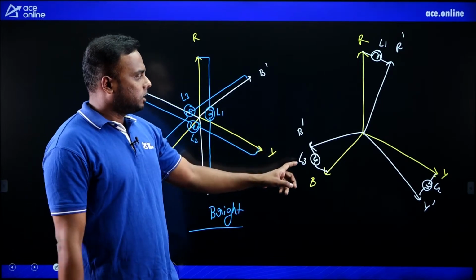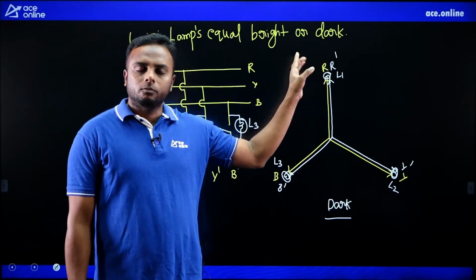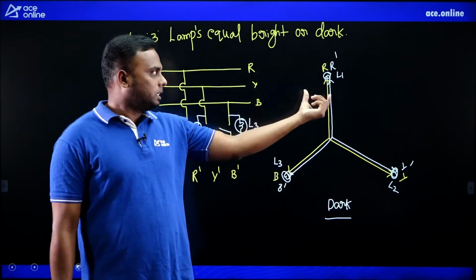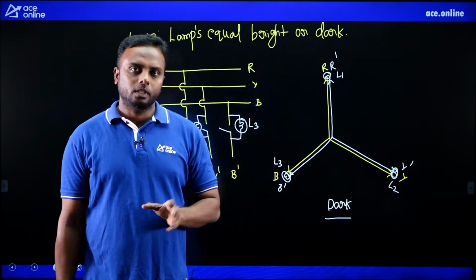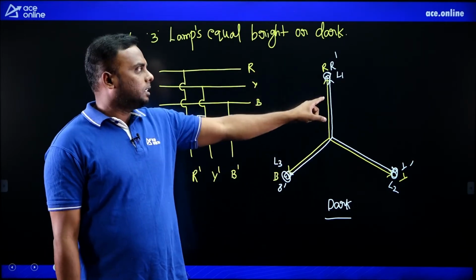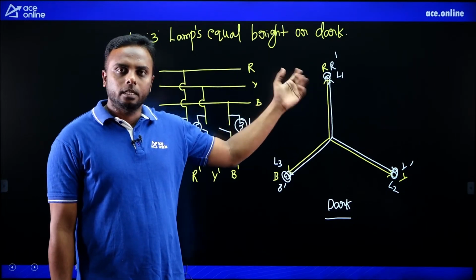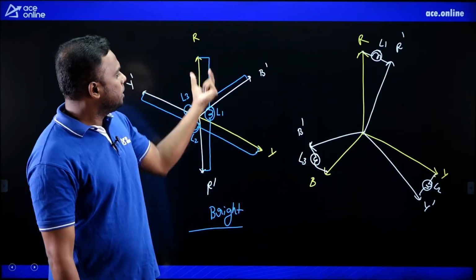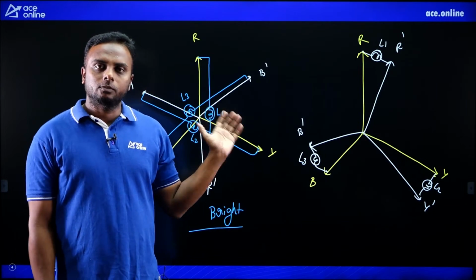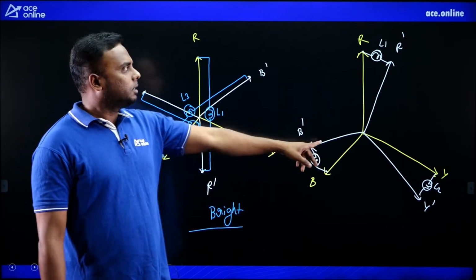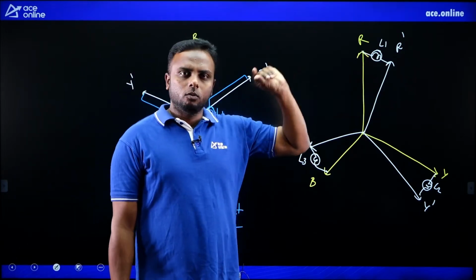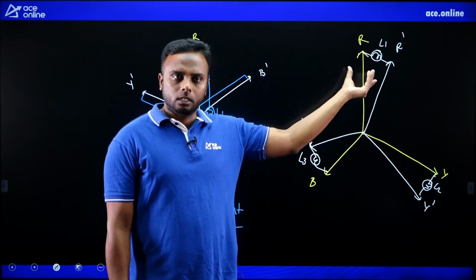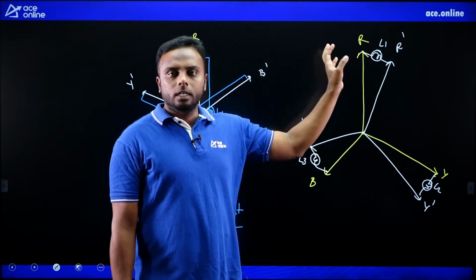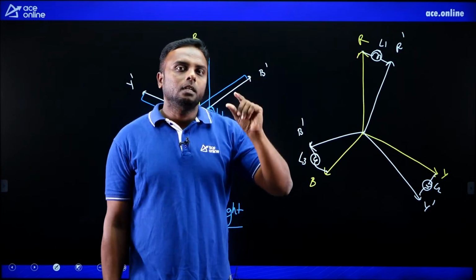Now in the first position, what is the voltage difference across the lamp? Zero, both are in phase, so since voltage is zero, the lamps will not glow, completely dark. And in the second position, there is maximum voltage difference, so we get brightness. And here there is some small voltage difference, maybe 10, 20, or 30 volts, so due to that small difference it has to glow with a little brightness.